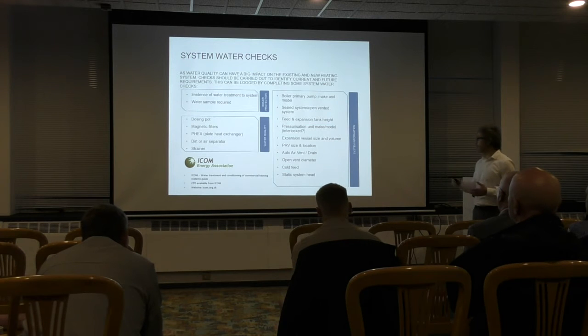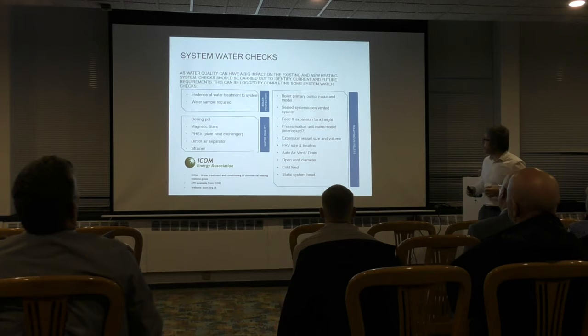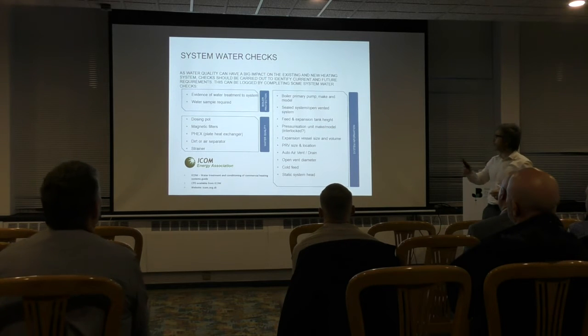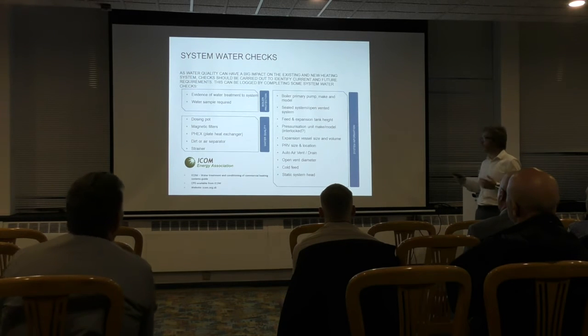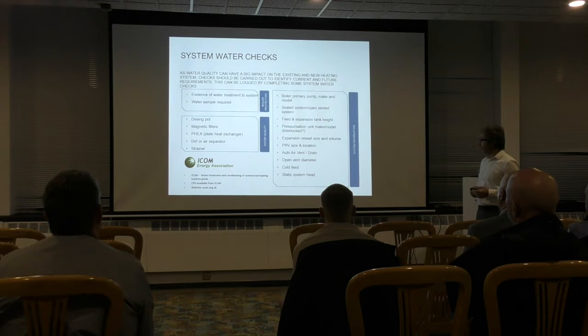So, the sealed system: you've got expansion vessels, what's the size and volume of that? The PRV size and location. Obviously there's also an air vent as well, and the drain, we need a suitable drain there. The open vent diameter was worth making note of. Obviously we need a suitable cold feed. But then the final point there, I think, is probably one of the most important points.